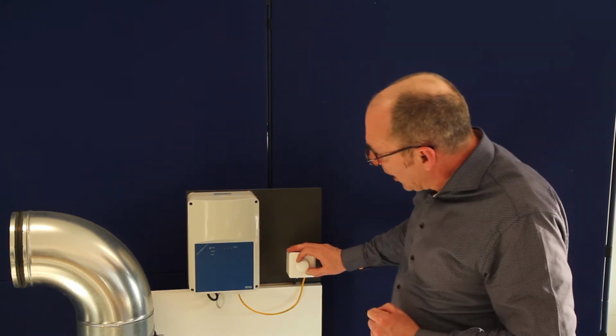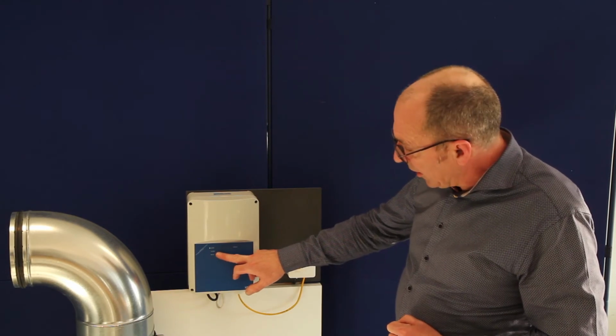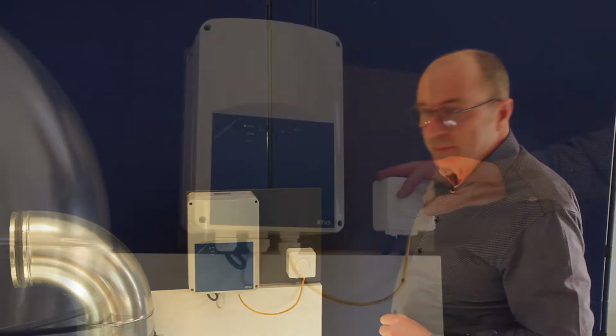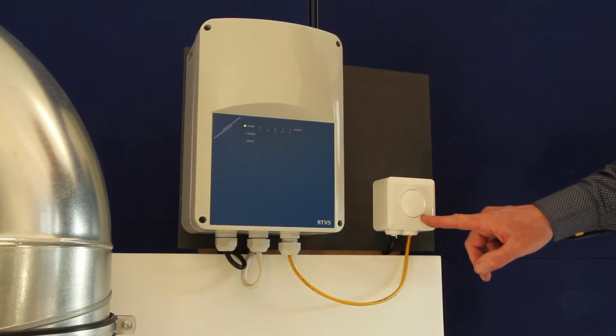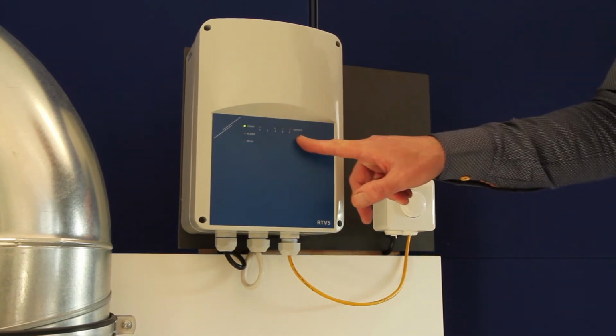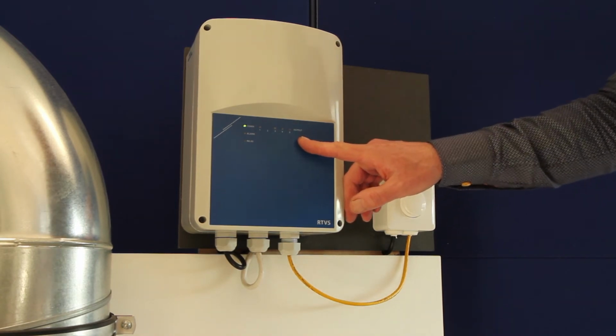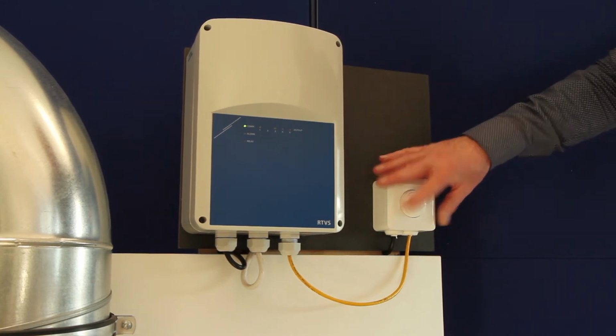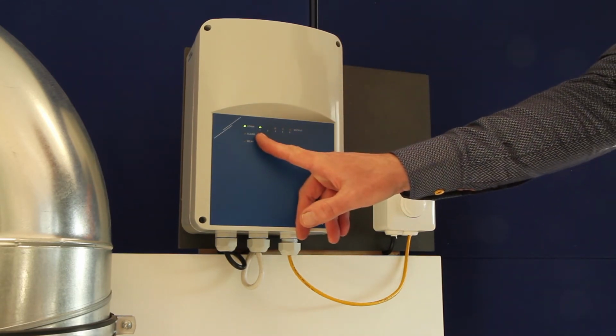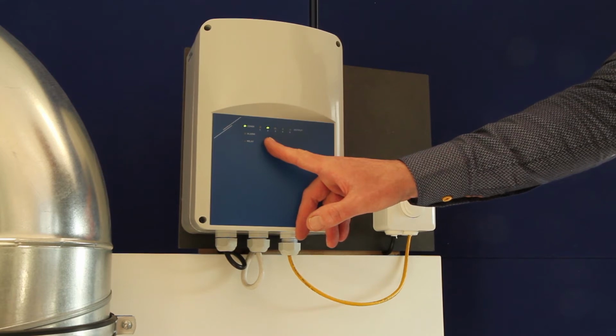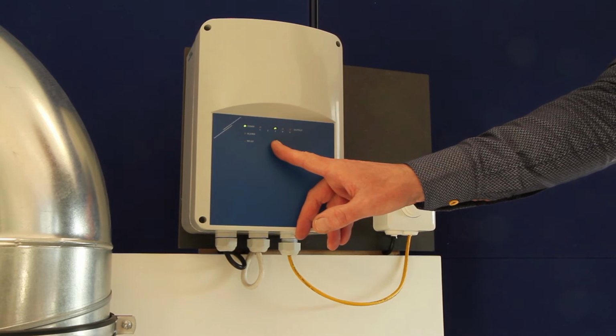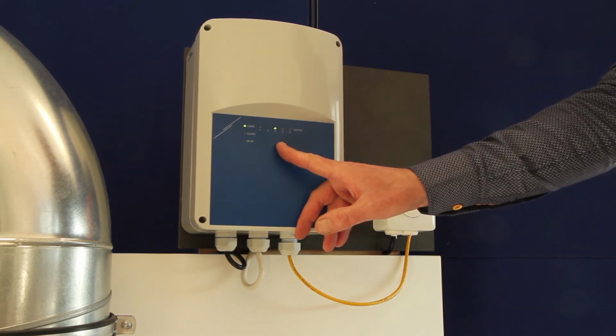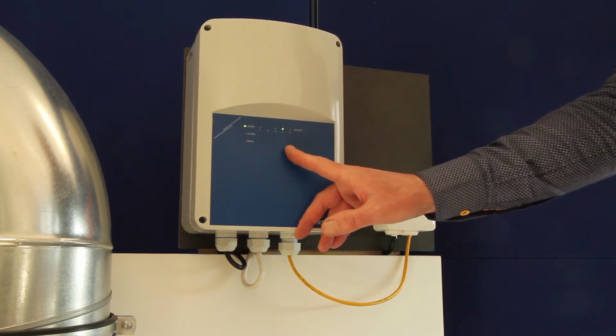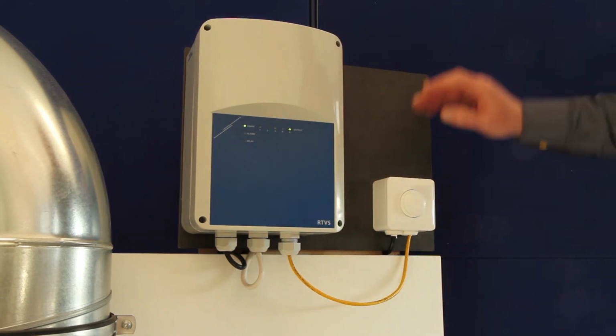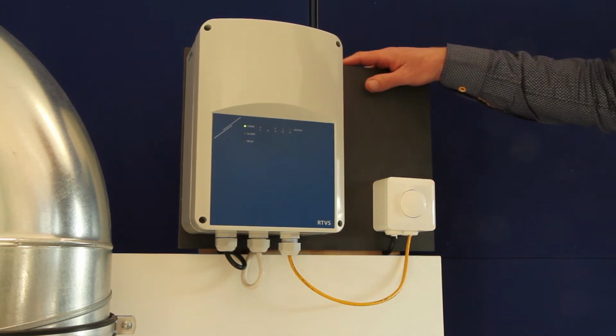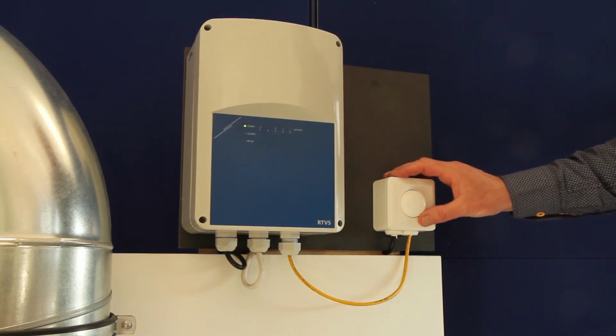I'm now going to demonstrate how it works. I'm going to increase the speed with the potentiometer and you will see that the device switches with some delay from speeds 1 to 2, to 3 and to 4. You will also be able to determine this by means of the LEDs on the device. I'm going now to turn the potentiometer all the way to the far right position in one movement. You will see that the speed increases with an interval of 5 seconds, which is actually a bit too fast. In practice, the speed should upshift more slowly, but anyway, for demonstration purposes, we set it to 5 seconds. You have noticed that when switching off to the 0 position, the unit stops immediately.